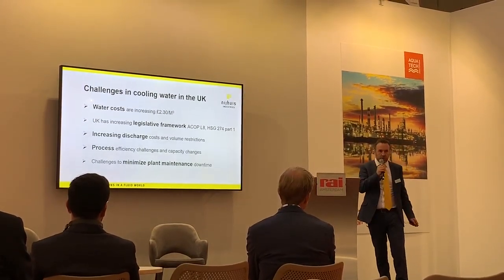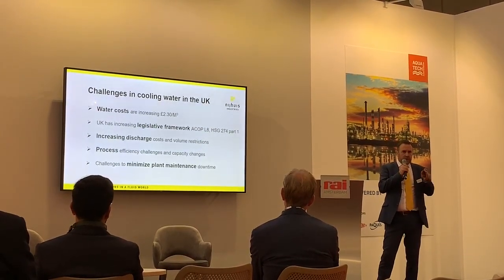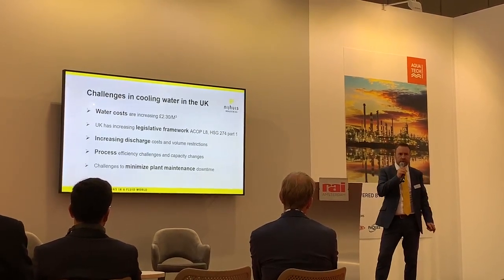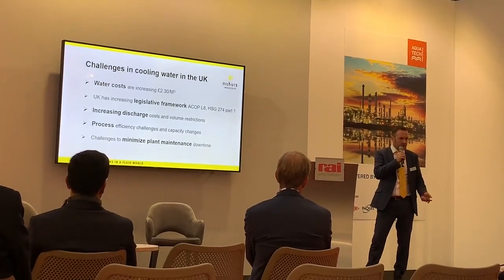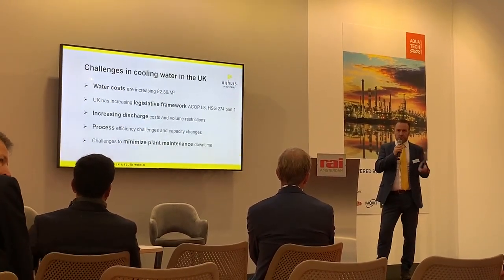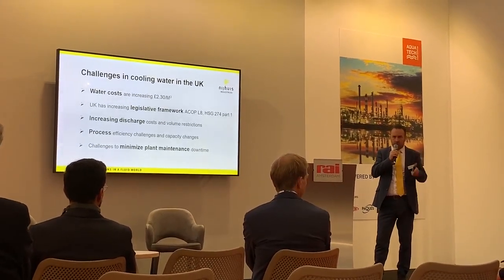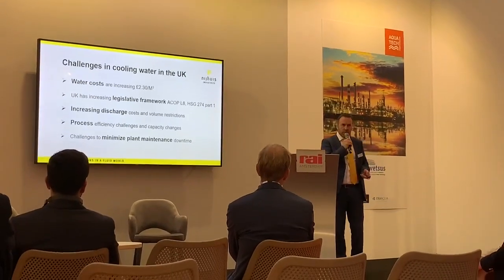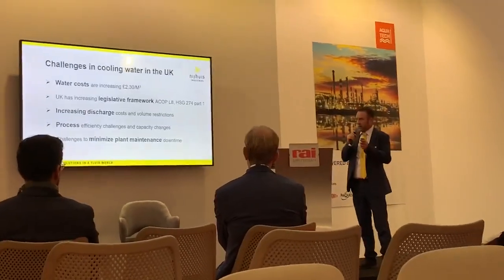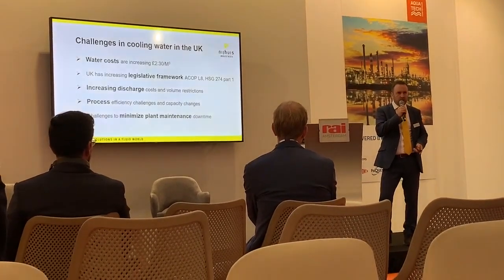And all of these things were driving the project, particularly the Legionella part, because the particular cooling tower is on a food factory which has a lot of canning and bottling facilities, and the contamination was coming from fat soils and greases, and it was accumulating in the system and causing biofouling, biofilms were forming, and as a consequence the bromine dosing was very sporadic, up and down, and correspondingly the microbiology results was up and down as well. The fouling was causing issues in terms of downtime, maintenance, heat transfer problems, and the system had to be cleaned on a regular basis as well. So all these things transpired to give a headache to the plant operators.